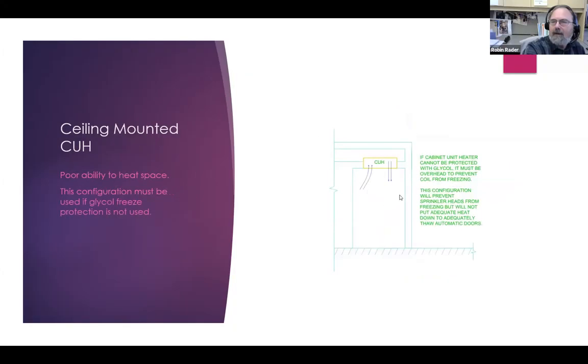This is a ceiling cabinet unit heater. These don't work well. They do keep the sprinkler head from freezing, but that is about it. They can't warm any occupants. The heat stays on the ceiling, and it's just a poor way to do it. However, if you are not running glycol in your heating system, you're forced to use a cabinet unit heater in this configuration. Otherwise, you'll freeze the coil.